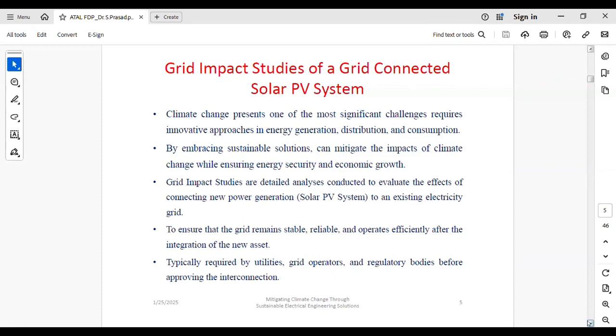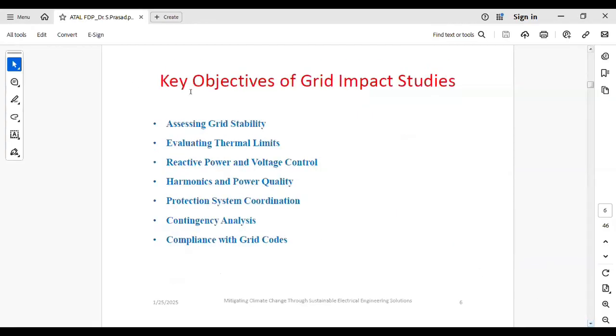And these studies we have to submit to the utilities. So the key objectives of the grid impact studies are assessing grid stability. That means when we are integrating the PV plant to the grid, because of the integration, it should not create any kind of issues or instability issues like voltage or frequency instability. So those issues should not be created because of the injection of the PV at the grid bus.